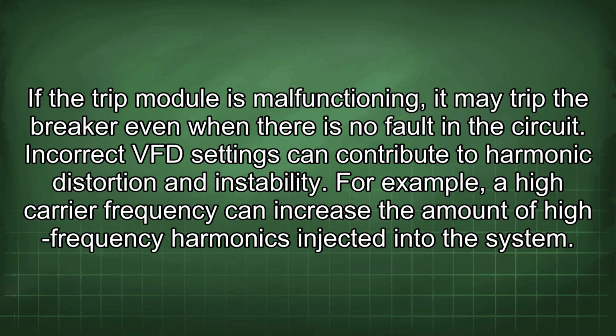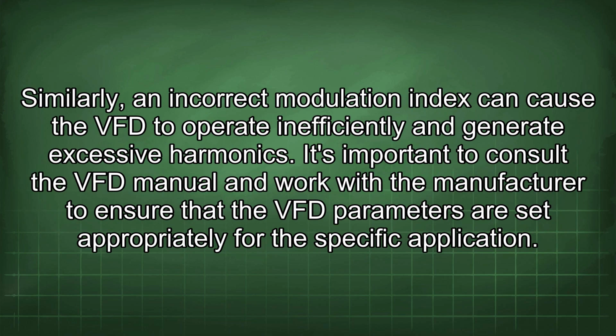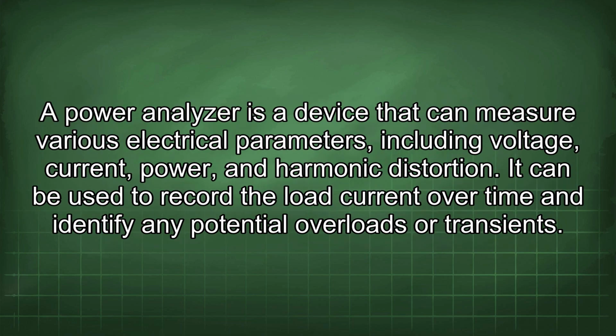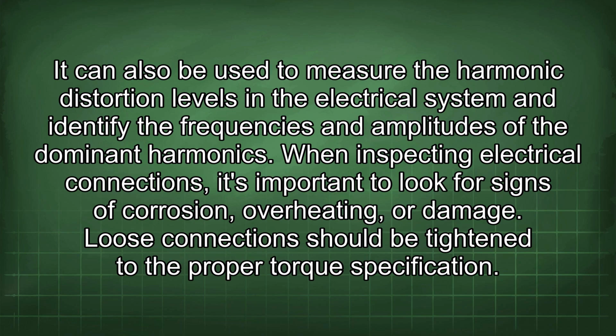Incorrect VFD settings can contribute to harmonic distortion and instability. For example, a high carrier frequency can increase the amount of high-frequency harmonics injected into the system. Similarly, an incorrect modulation index can cause the VFD to operate inefficiently and generate excessive harmonics. It's important to consult the VFD manual and work with the manufacturer to ensure that the VFD parameters are set appropriately for the specific application. A power analyzer is a device that can measure various electrical parameters, including voltage, current, power, and harmonic distortion. It can be used to record the load current over time and identify any potential overloads or transients. It can also be used to measure the harmonic distortion levels in the electrical system and identify the frequencies and amplitudes of the dominant harmonics.